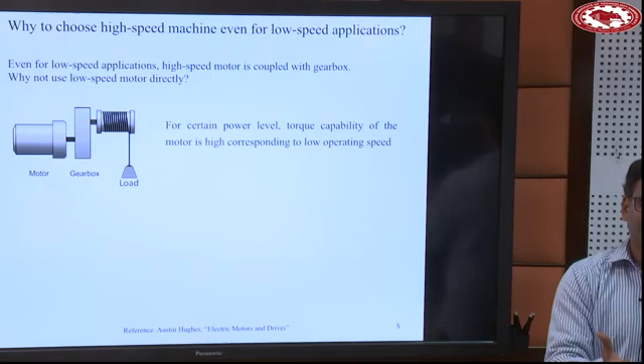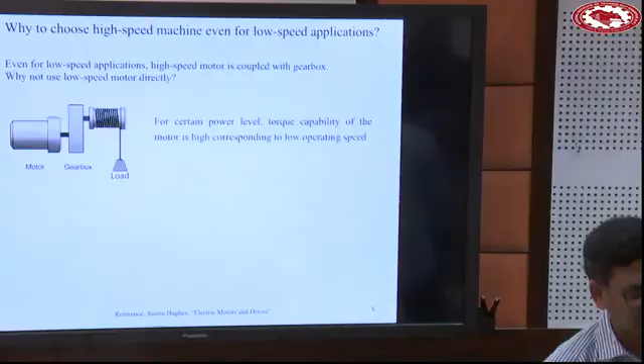Yeah, if the speed is high, keep the left hand side, power is equal to torque into speed, okay. Keep the left hand side the same, because 3 or 4 persons are standing, so how much power is required? Let's say 20 kilowatt required. So left hand side is fixed power. Power is equal to torque multiplied by speed. Suppose if we go for a low speed motor, I want to get rid of the gear system. When you are eliminating the mechanical system, the efficiency of the overall system improves. How does it improve? Because the gear system, although we introduce it, is not 100% efficient. So it is 95%, some 5% of mechanical transmission loss is gone.